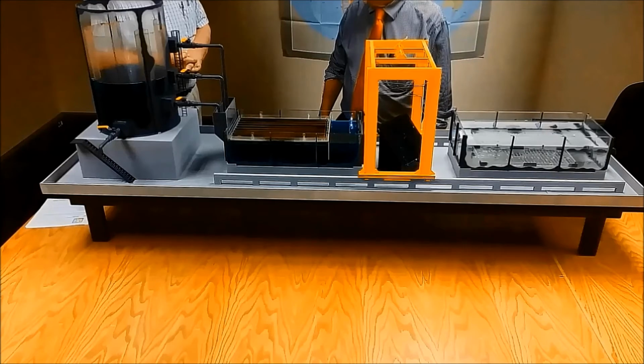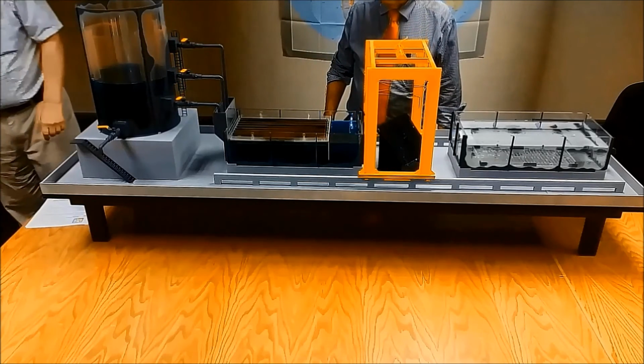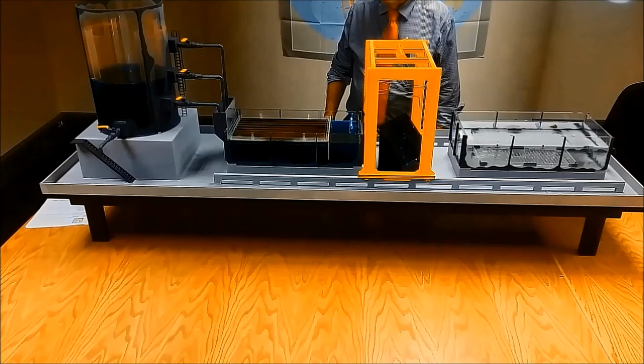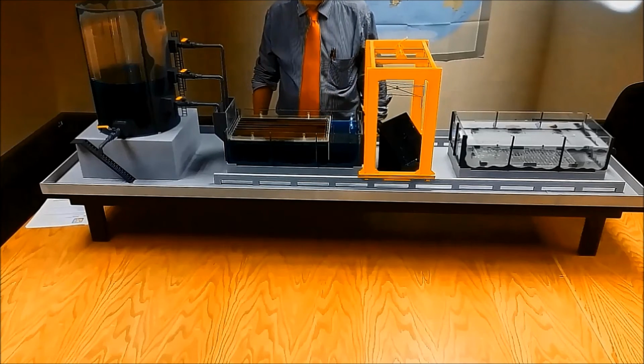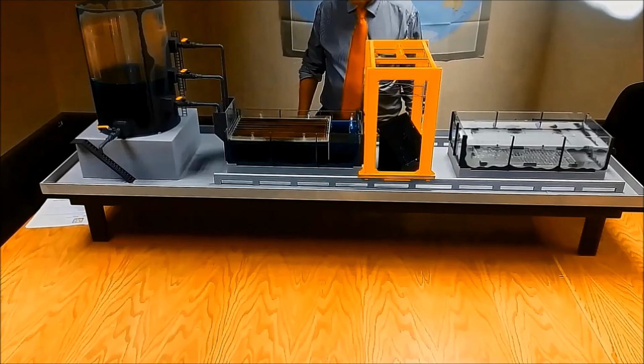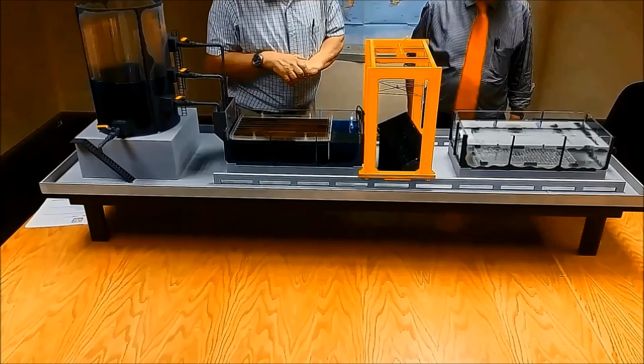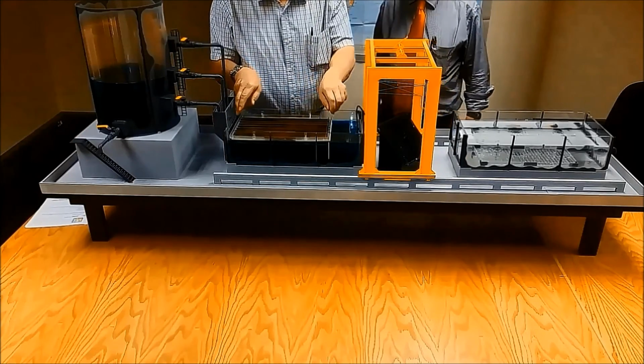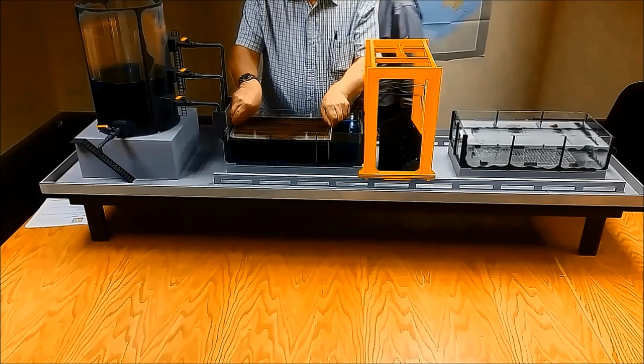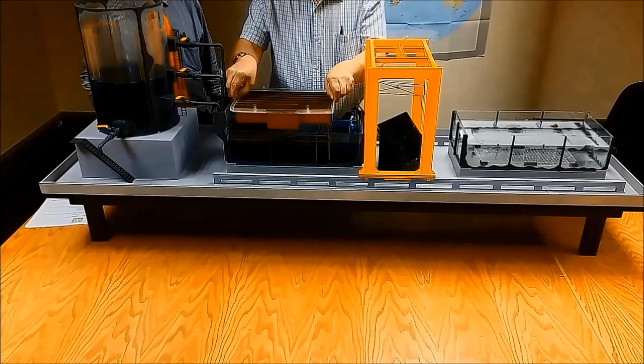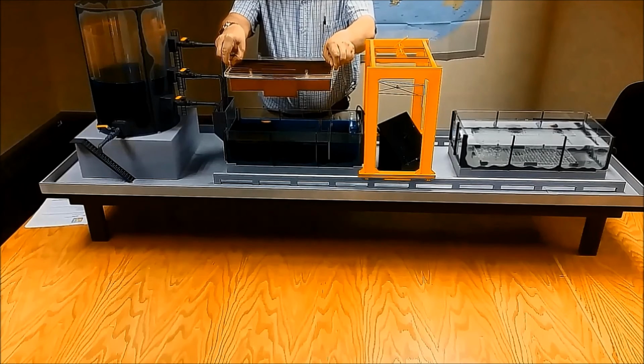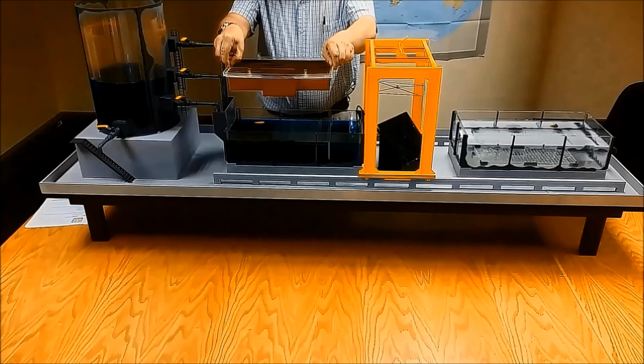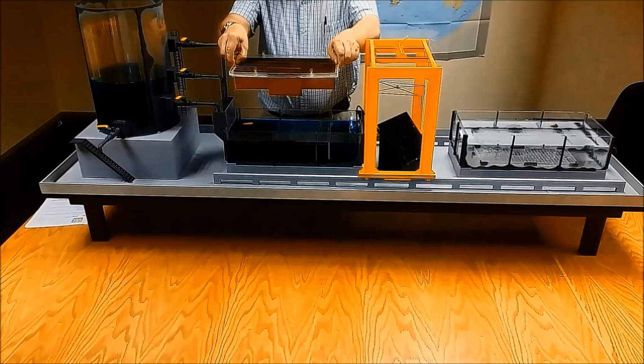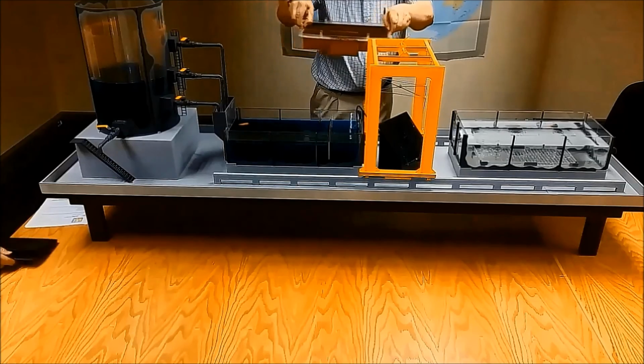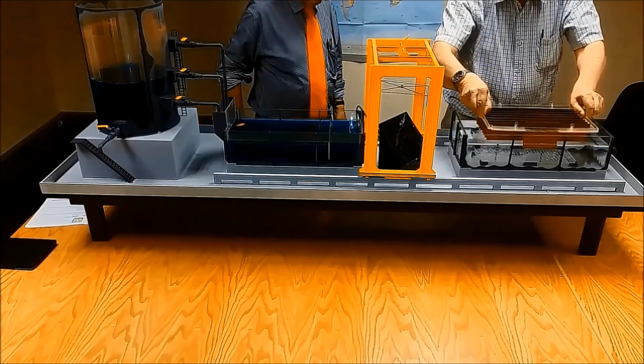The process takes approximately 5 minutes. After 5 minutes, the probe rack is removed from the recovery vessel. Note the flakes of copper floating on the surface. The excess solution is then allowed to drain back into the recovery vessel. The probe rack is then placed in the storage vessel rather roughly to promote the copper flakes gravitating to the collection basket at the bottom of the vessel.